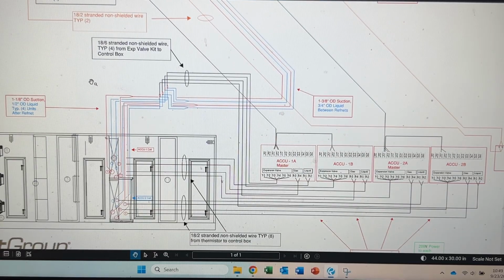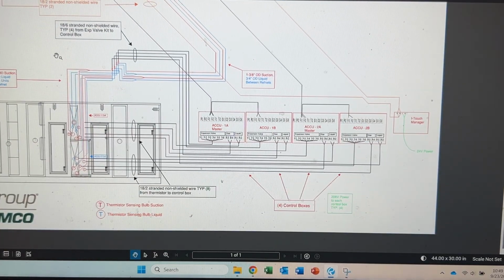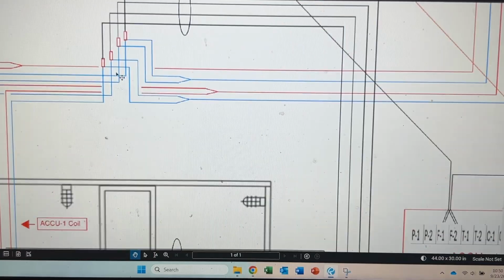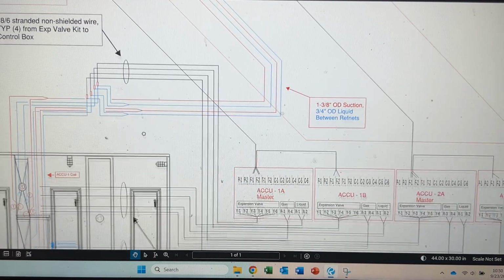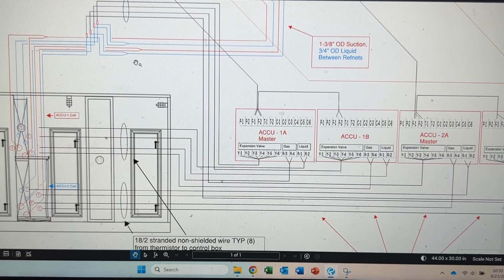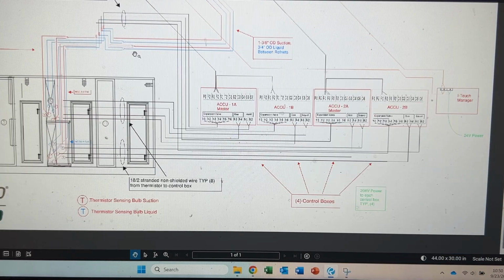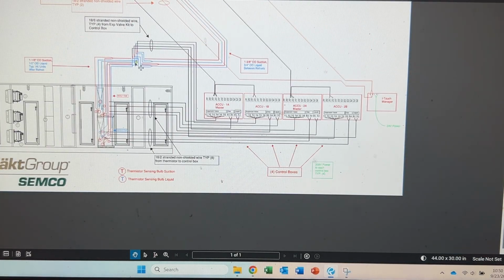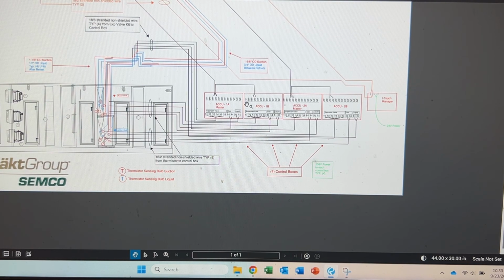What was cool, the expansion valve kit for the air handling unit - I've yet to install this style before, so that was pretty neat. These expansion valve kits are only on the liquid line. So, expansion valve kit, we got 4 of them, for the 4 liquid lines that service each of these coils, 2 and 2 - 2 for circuit 1, 2 for circuit 2. And they go back to these control boxes.